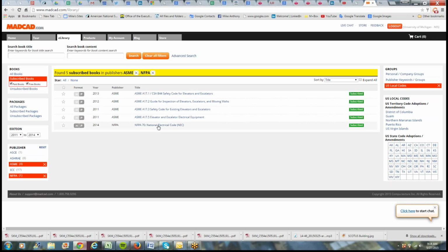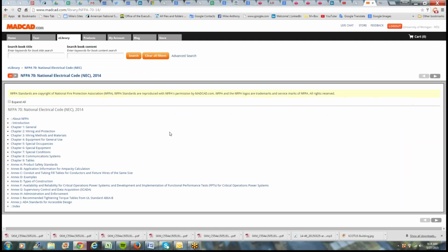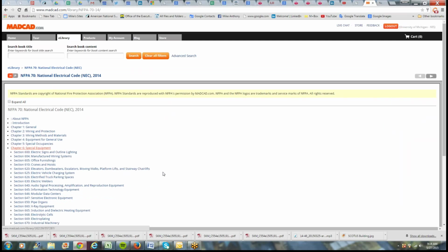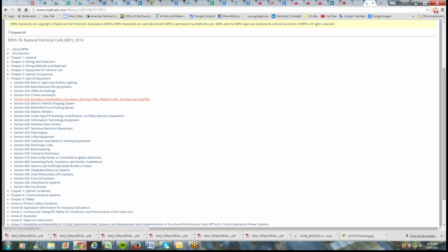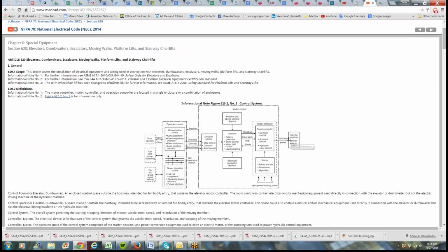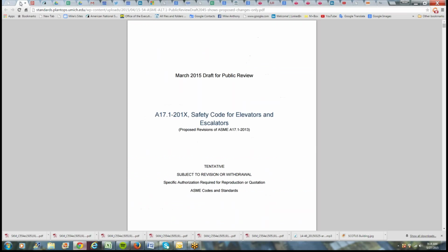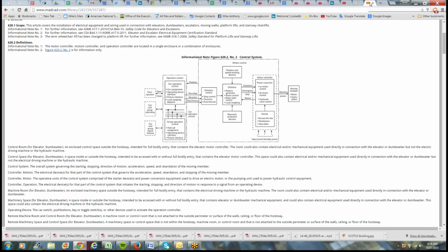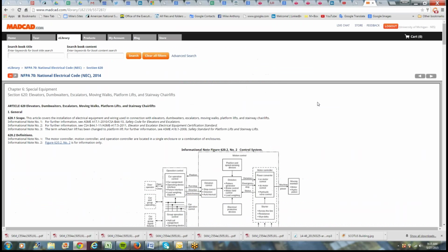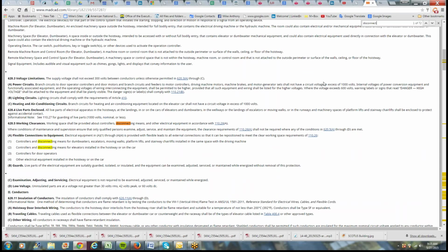And they'll tell you that, well, you can drift the car, but you have to have access to a method to drift it in order to do it. So there's always an issue. If the safeties are set, you can't get to it because you have to release it. The national body of the A17 Standards Committee voted to approve that they could use a disconnect switch outside the hoistway anywhere in the building. And it didn't even say that it had to be in the same building.